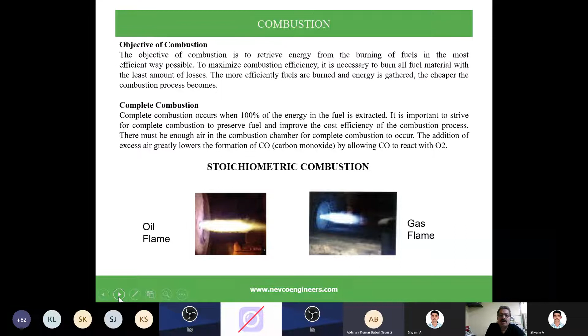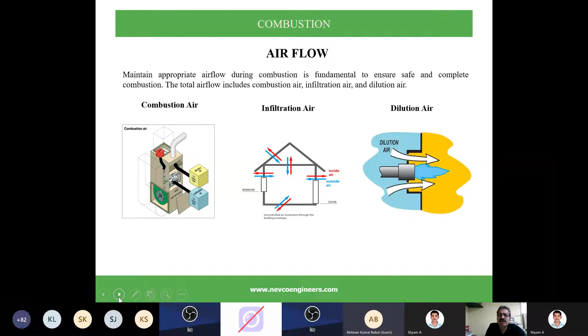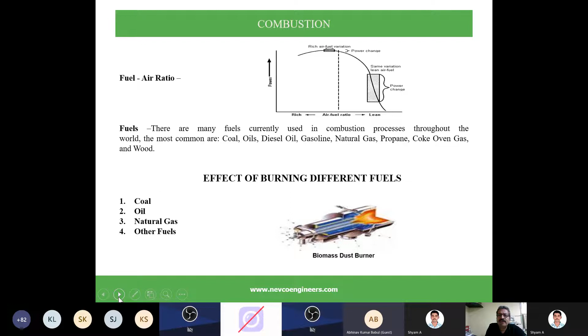So these are two different flames, oil and gas fired. As I said, there is extra air and there are different types of airflow. Maintaining appropriate airflow during combustion is fundamental to ensure safe and complete combustion. The total airflow includes combustion air, infiltration air, and dilution air. This is the air fuel ratio. There are many fuels currently used in combustion processes throughout the world. The most common is coal, mostly in our power plants. But also oil, diesel oil, natural gases, propane, coke oven gases, and woods.